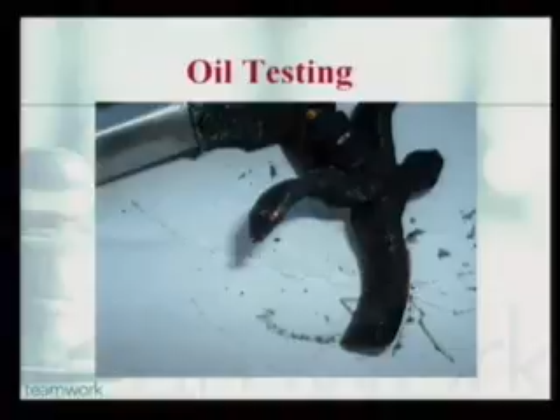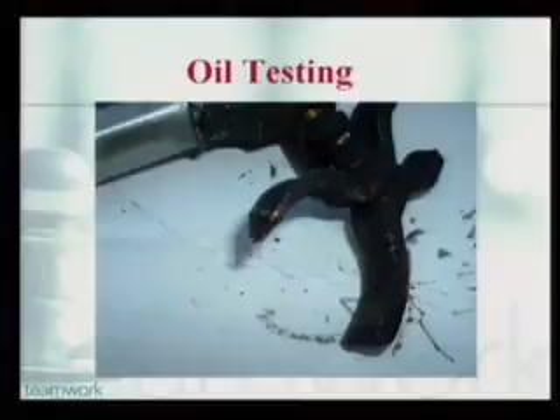Ramon, is that due to a manufacturer defect or is it something else? It's just, these are moving parts. As you can see, it's copper, and sometimes they get caught. And during the abrasion, there's some movement there. And that's the thing that we have to watch out for. I wish I could call it a manufacturer's defect. Unfortunately, I can't. This transformer has been operating since 2003, I believe. So it's been 5 years. And just to reiterate, this was determined during preventive testing? Yes. Okay. This is the benefit of doing the transformer oil testing that we do. We're able to catch problems before they fail. These are red flags.